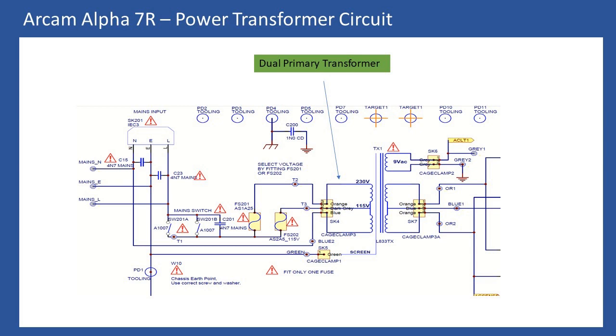The same applies to the protection fuses. I'll show it in the video, but your protection fuse FS201 is a T1.25 amp protection fuse. Sometimes a user has a failure, investigates, sees the fuse socket which is FS202, and puts a fuse in there.